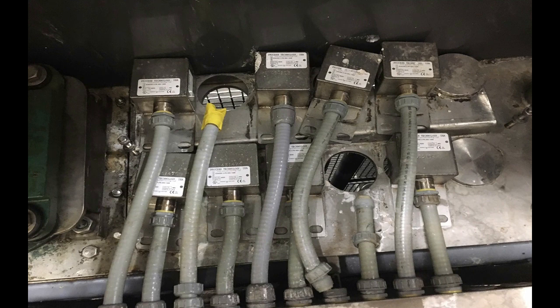This is a picture I collected from the field, showing a whole group of modified metal heaters installed in a single tank. I can see a total of eight heaters installed, when in fact there are actually spots for four more. So this one tank is going to have 12 immersion heaters installed, and for the electrician doing the wiring, that means he has to manage 12 conduits and 12 sets of wires.